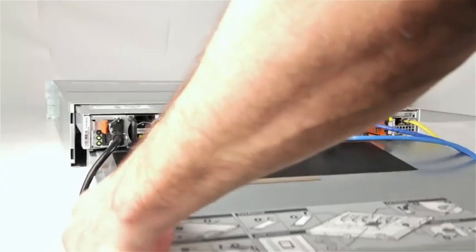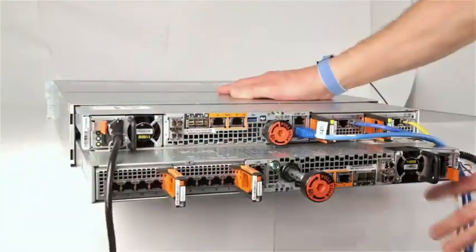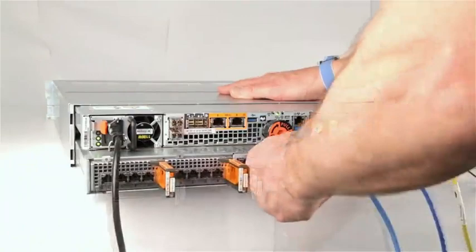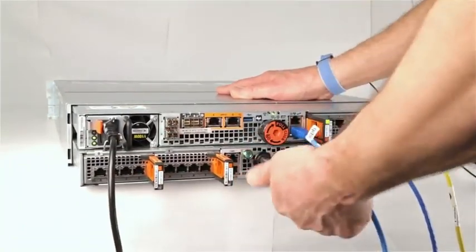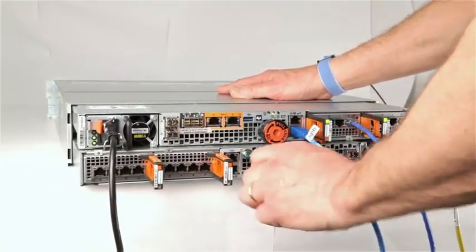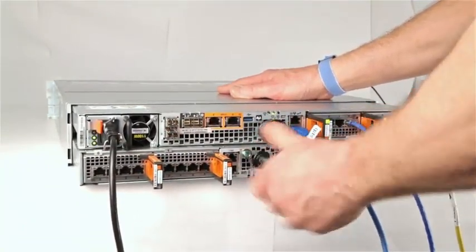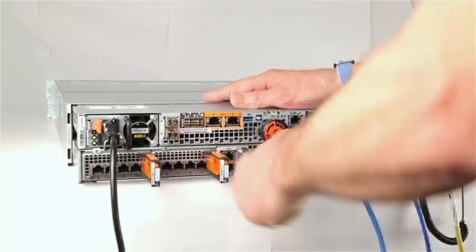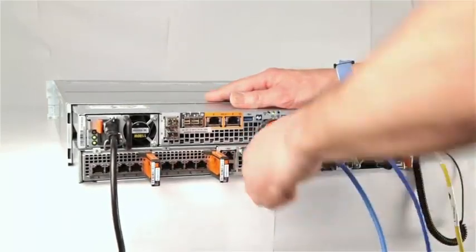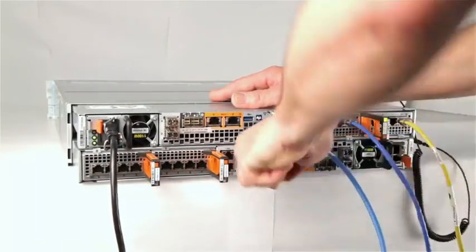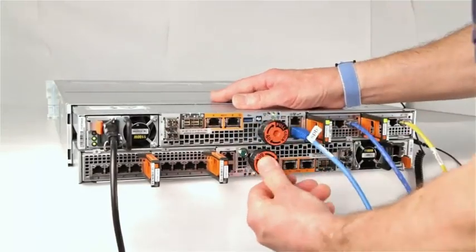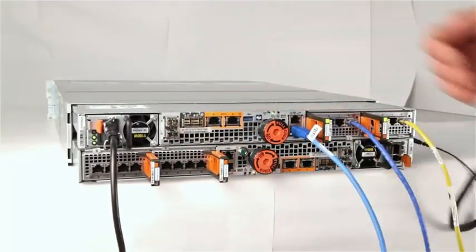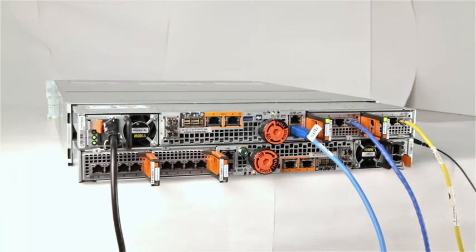Align the SP assembly with the enclosure slot and slide it into the slot until it stops. Turn the orange torque limit screw handle clockwise until you hear a click sound from the handle. The click sound indicates the torque limit is reached and the SP is seated fully in the enclosure. Push the orange torque limit screw handle into the SP assembly until you hear a click again. The click indicates the screw handle is secured in the assembly.